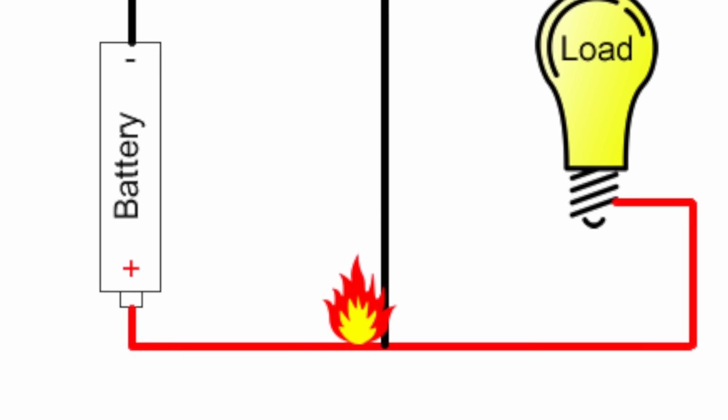High resistance can be a bad connector where it is just not getting through. Low resistance is probably going to be a short circuit where it's looking for a less resistive path to go through. And that usually is a cut wire touching a frame, a metal frame somewhere. There is fluctuating amperage in that front array, all over the place, all day long.